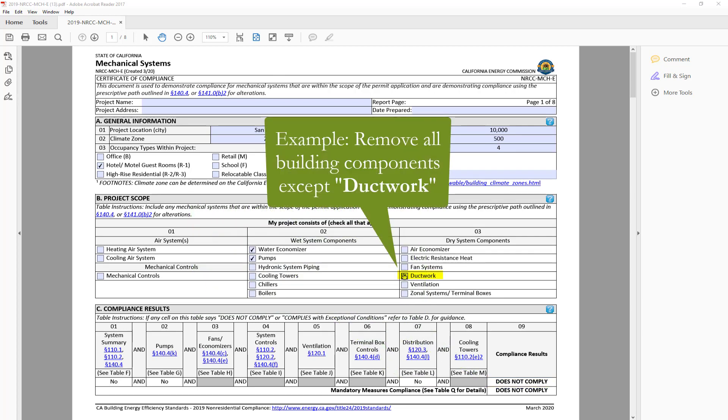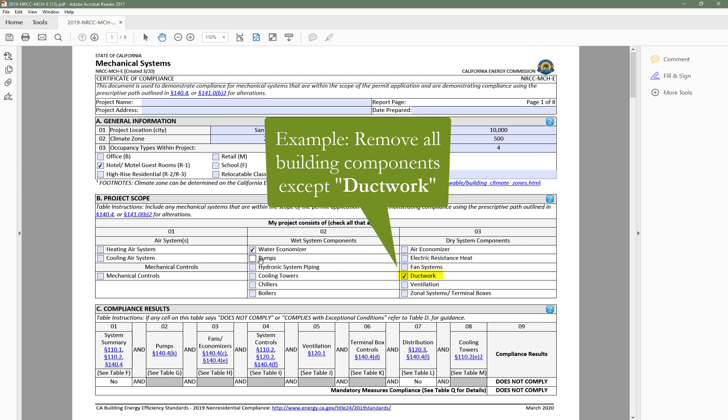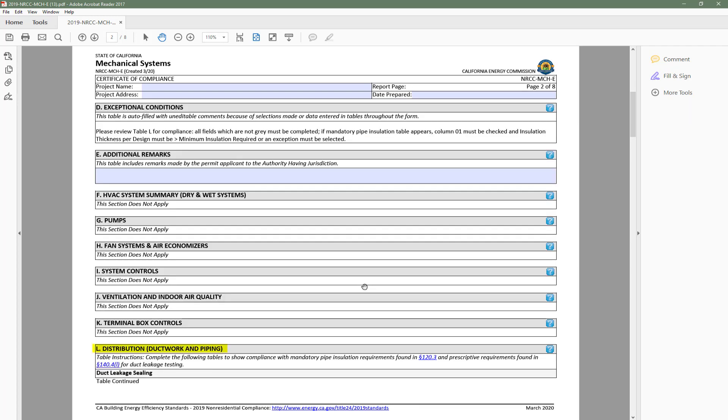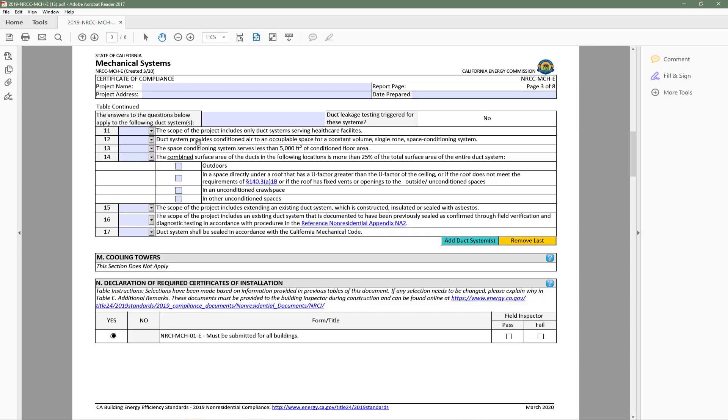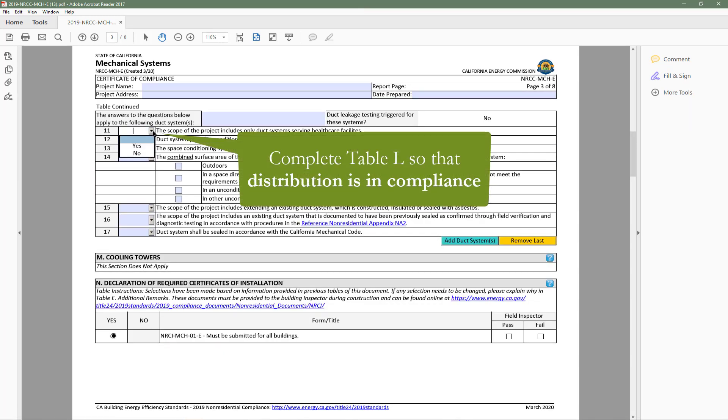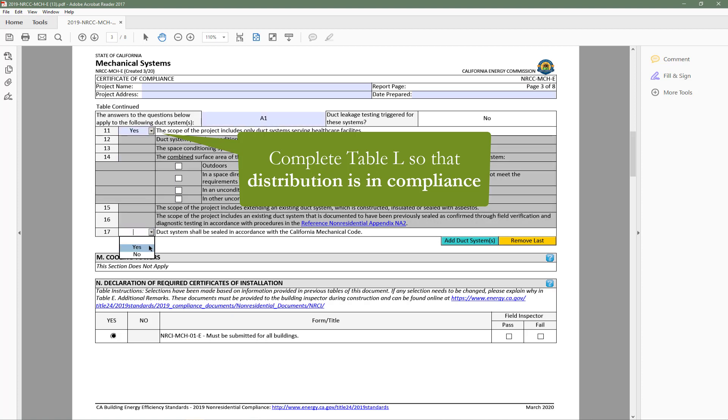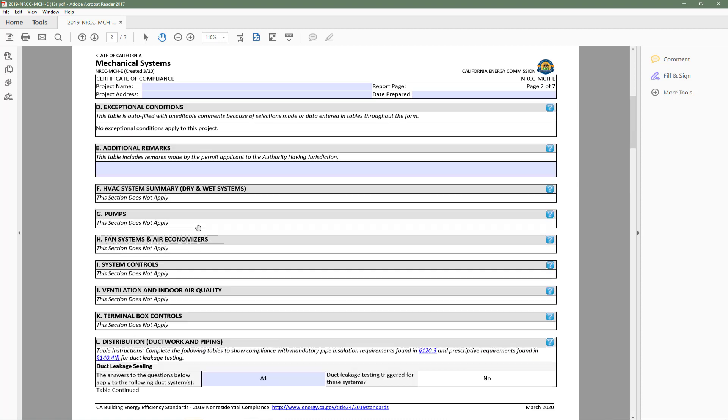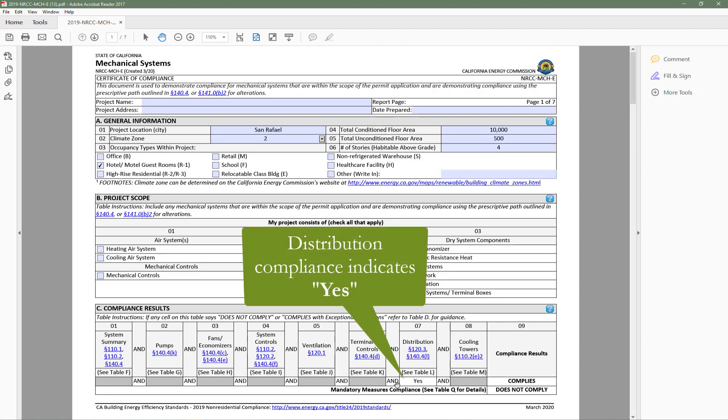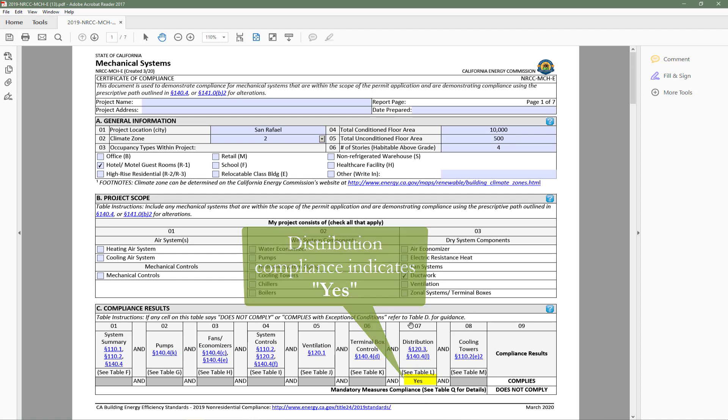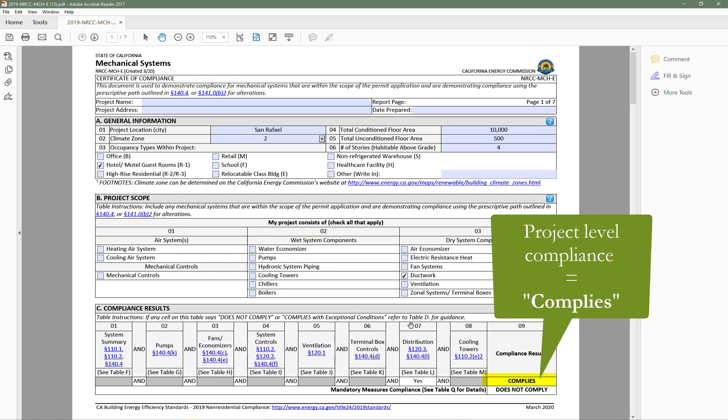For example, if we remove all building components from Table B other than Duct Work, head to the Distributions Table, which is Table L as indicated in Table C, and quickly fill out the table so that distribution is in compliance, we will head back to Table C, and you will notice that the Distribution column says Yes, and as a result, Table C indicates complies at the project level.